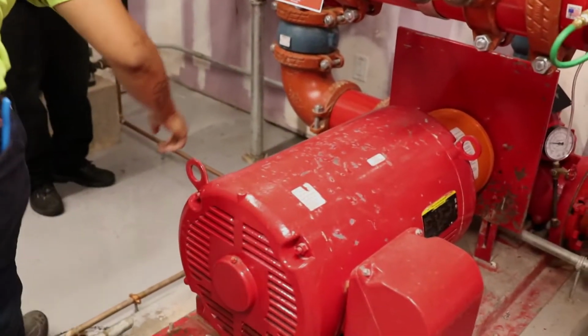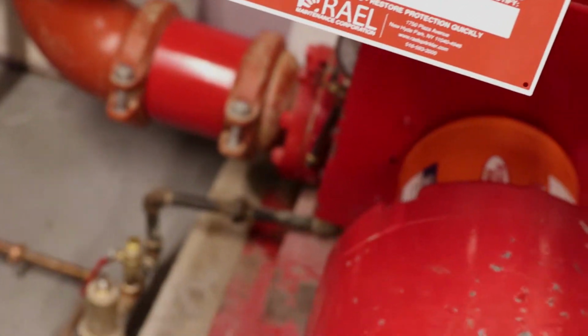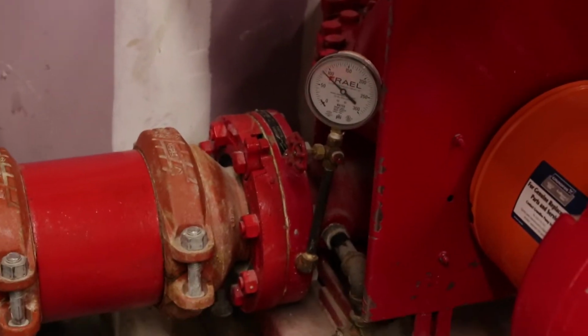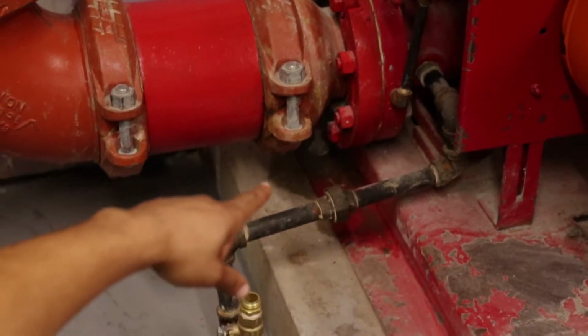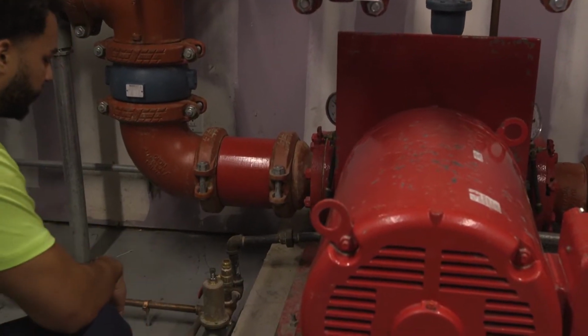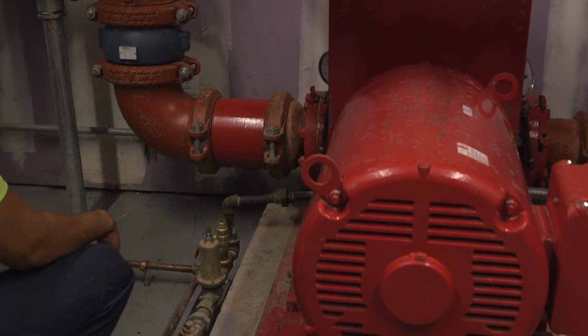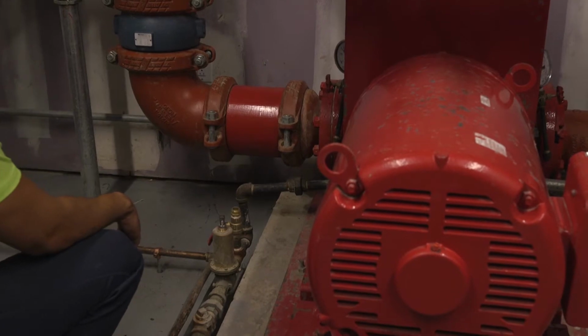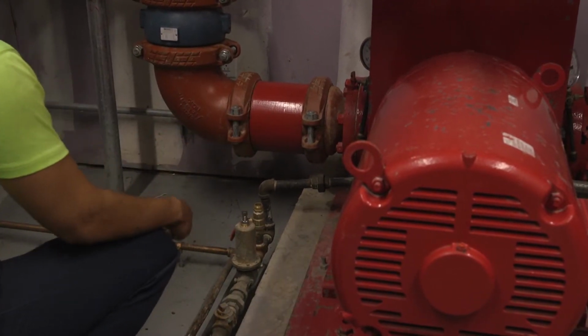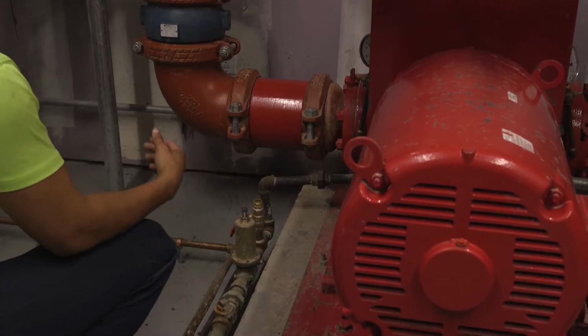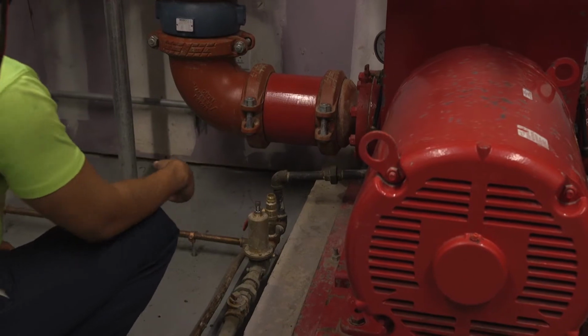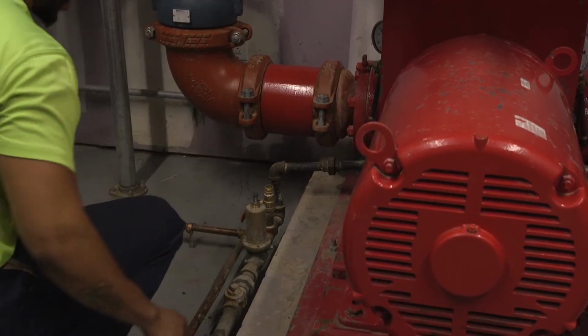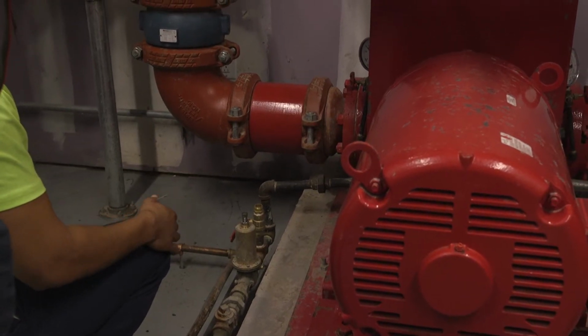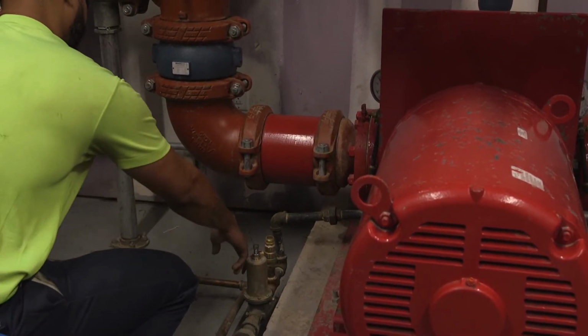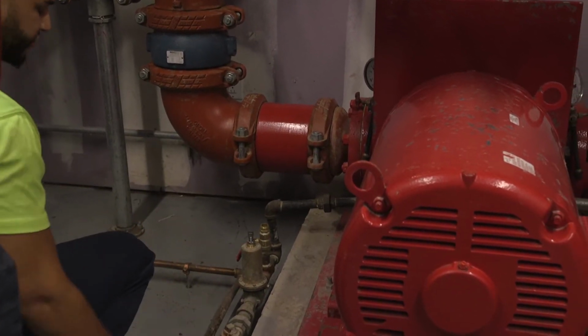Our discharge and our suction pressure gauges should be reading relatively the same PSI, maybe about 5 or 10 pounds above or below. Here we have our casing relief valve, and it's piped directly at the discharge side of the fire pump. Our casing relief valve is the cooling mechanism for the fire pump. When this fire pump runs and we're not flowing any water, that is going to start causing heat, which in turn is going to start warping your impeller or burning out your fire pump packing. So this valve is going to open up and dump that hot water, and it's going to keep introducing cool water into your fire pump and keep it from overheating. And here we just have a bleeder valve just to bleed this line out.